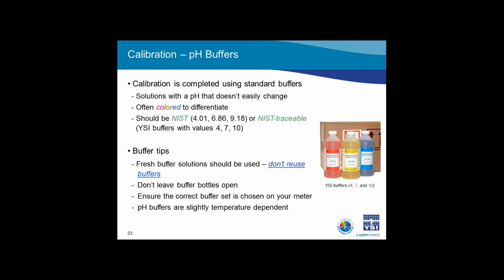Just as important as using traceable buffers is making sure your solutions are fresh and not contaminated. Old or contaminated buffers will introduce error in your calibration and subsequent measurements. So check the expiration date on your bottle and note that buffers actually have two shelf lives, one unopened and one opened. For example, YSI buffers have a 2-year shelf life unopened, but once you open it, the shelf life is reduced to 6 months. So check with the manufacturer of your buffer solution to obtain this information and write the date you open the buffer right on the bottle. Since transpiration or evaporation can affect buffers, make sure you close the bottles when you are done with them. If this becomes an issue, there are buffers available in larger airtight bags that will last longer.